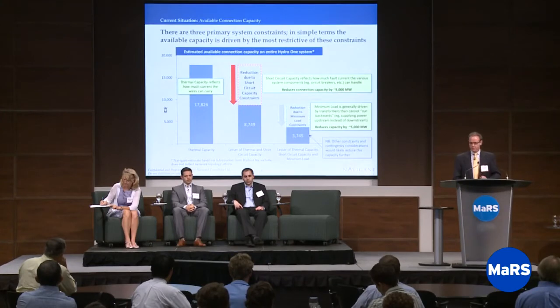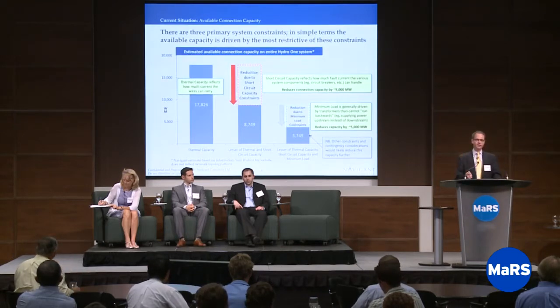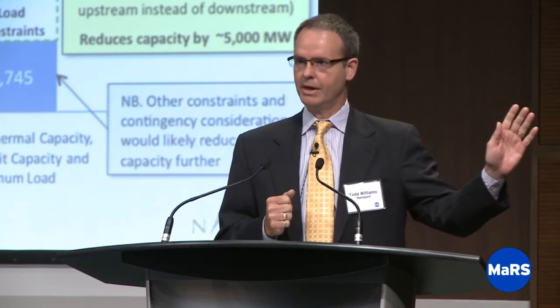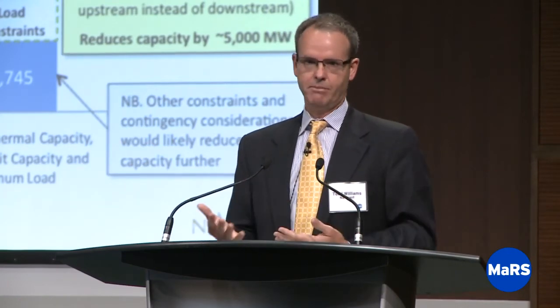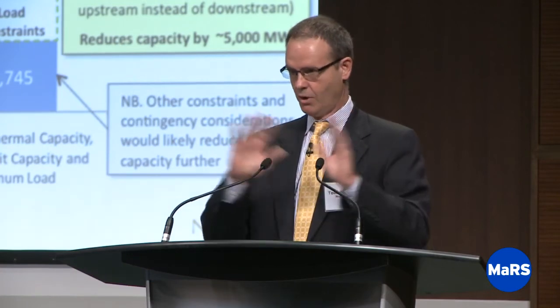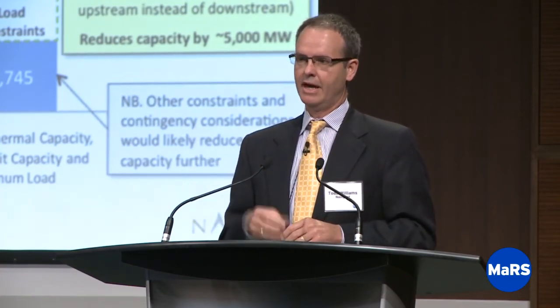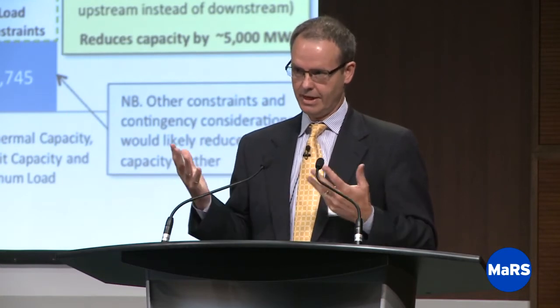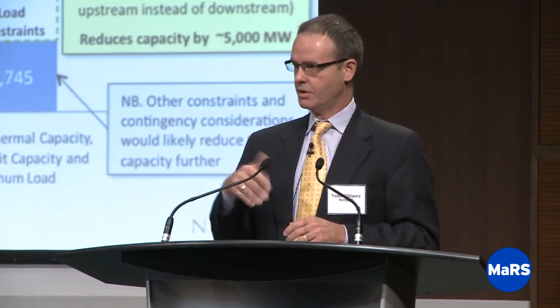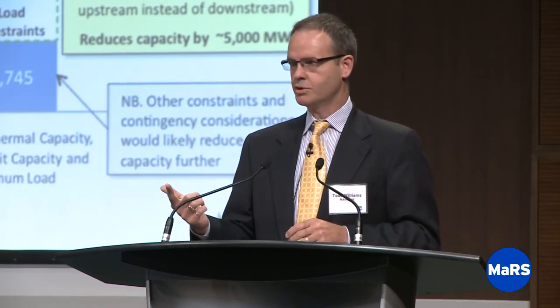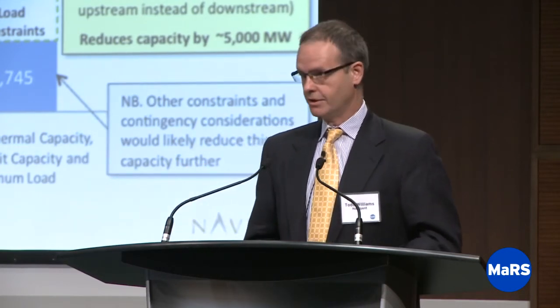If you go to the right, there's a reduction driven by short circuit capacity. Short circuit capacity is when there's a fault in the system. The generators, and I think a lot of the inverters can have discussions in terms of how much they'll contribute, basically try to fill that fault, and they pump current up the line across the network. All the components throughout the system have fault current limits, and if those fault currents are exceeded, they either explode or they fail. So it's not only a reliability issue, it's also a safety issue. If that happens, that's not good, obviously.